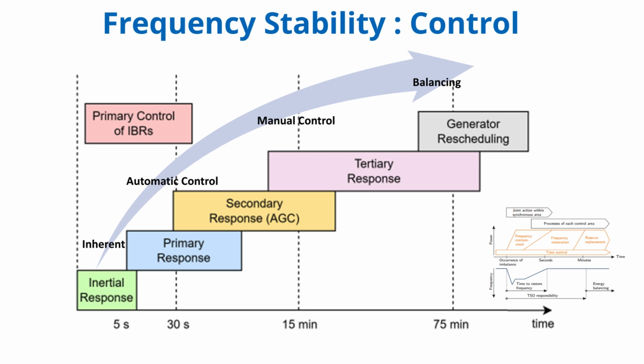Right. Automatic generation control operates over minutes. It's usually centralized within a control area. AGC looks at the frequency error and the power flow deviation on tie lines to neighbors. Ah, so it manages the area's overall balance. Exactly. It sends signals to specific generators to adjust their output more deliberately, aiming to bring frequency exactly back to the target value, like 60.00 hertz, and restore the scheduled power exchanges with other areas. It cleans up the error left by primary control.